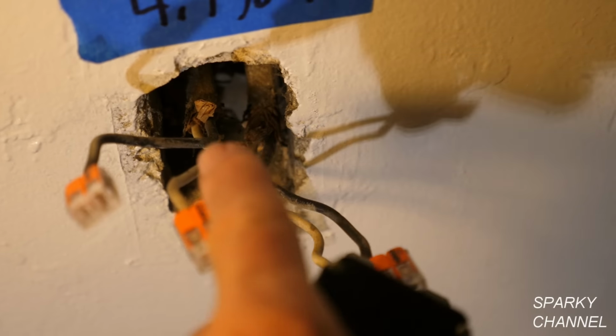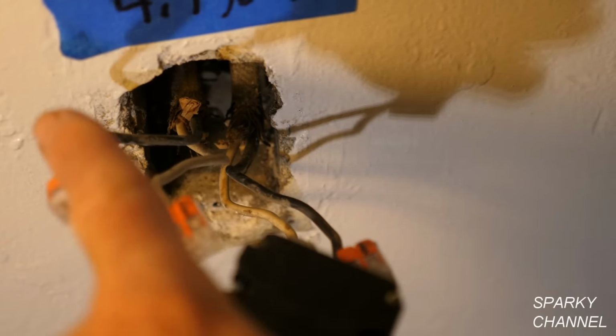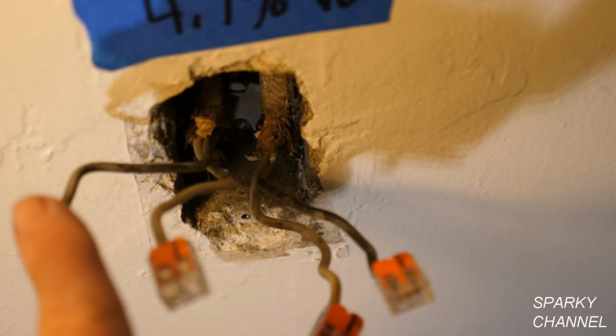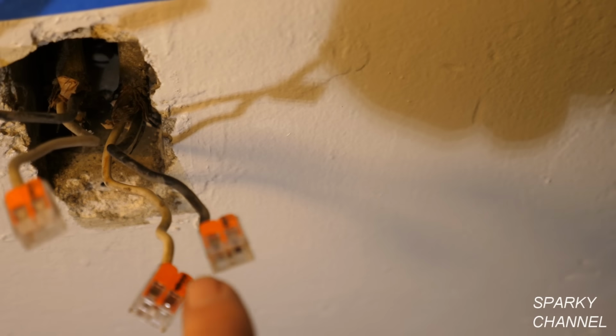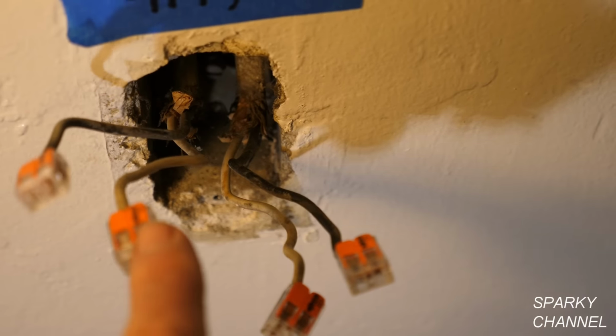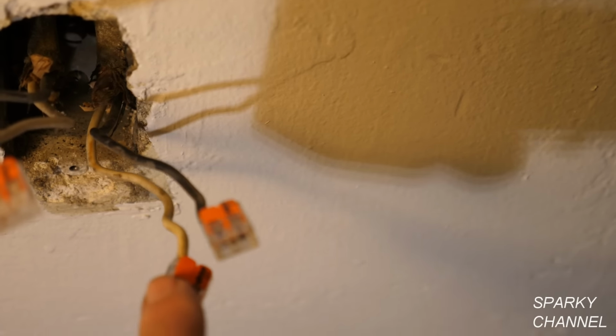So this right here, the one that tested hot, this is your line cable right here. That's one of the reasons we tested. We need to know that this is the line. So this is the load. This carries the electrical energy into this box, and the load carries the electrical energy to the next receptacle. I'll start with the neutral and put it to the silver terminal.